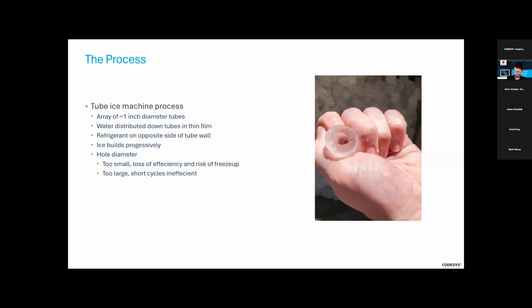When we're looking at that hole, we want to be at a size that gets us the most tons of ice per hour when we're doing fresh produce. If you're doing bagged ice that needs to go to the store, you need to get 20 pounds of ice in that bag. And then you may need a little bit tighter hole just for volume reasons. But for produce, we want maximum ice. And what we found on the inch and an eighth tube machines is that's about the size of a pencil.